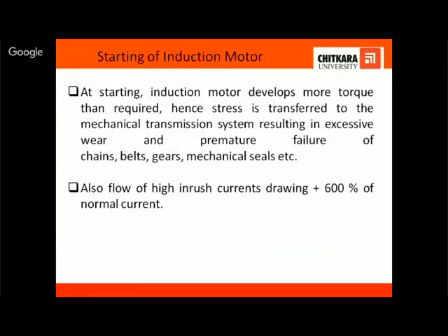Now coming to the starting of induction motors. We all know that at starting the induction motor develops more torque than required, and that stress is transferred to the mechanical transmission system, resulting in excessive wear and premature failure of the chains, belts and gears. And at starting there is a high inrush current flowing in the system, which is normally 6 times the normal current.